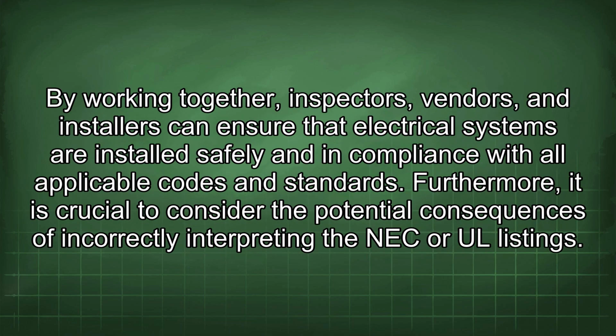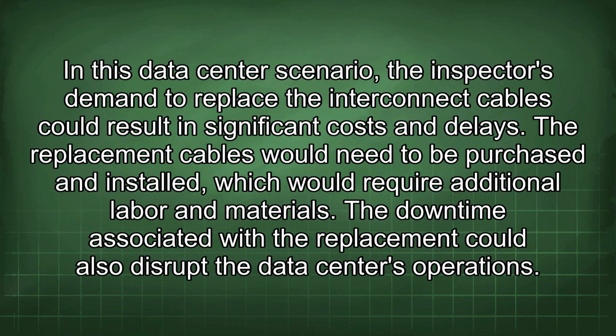By working together, inspectors, vendors, and installers can ensure that electrical systems are installed safely and in compliance with all applicable codes and standards. Furthermore, it is crucial to consider the potential consequences of incorrectly interpreting the NEC or UL listings. In this data center scenario, the inspector's demand to replace the interconnect cables could result in significant costs and delays. The replacement cables would need to be purchased and installed, which would require additional labor and materials.